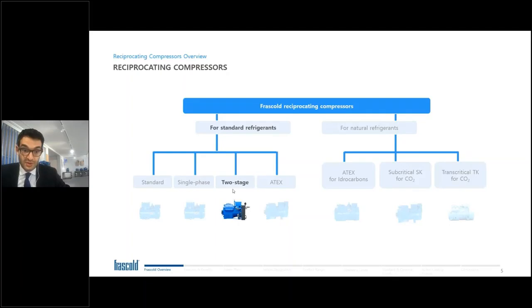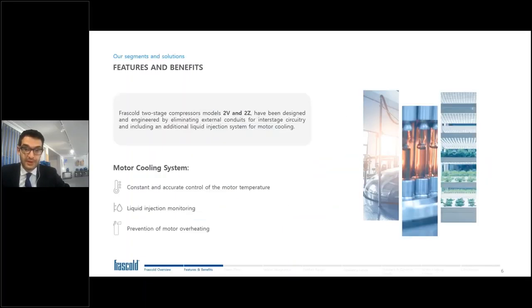And the two-stage compressors are also a little bit particular because the very low temperature applications are the only ones out of the F-gas regulation. So if you evaporate at -60, for instance, you are allowed to use R448, which for other segments is clearly forbidden. Let's see more in detail.